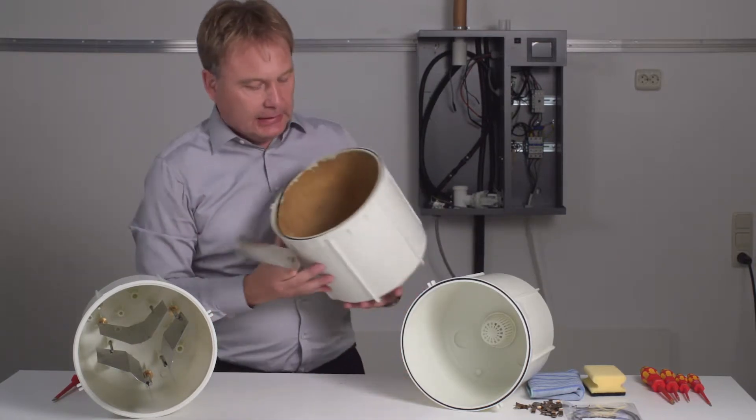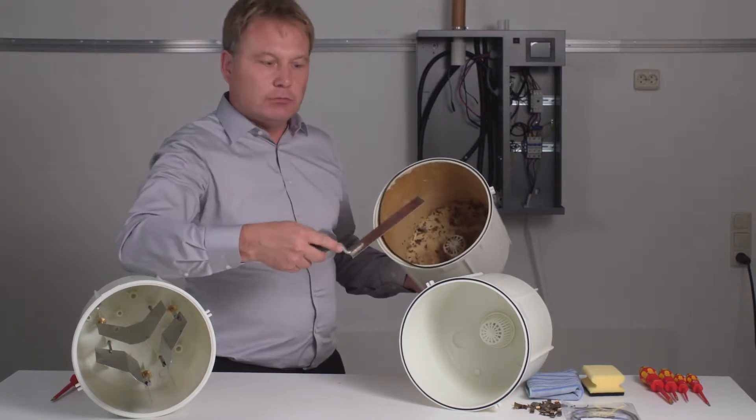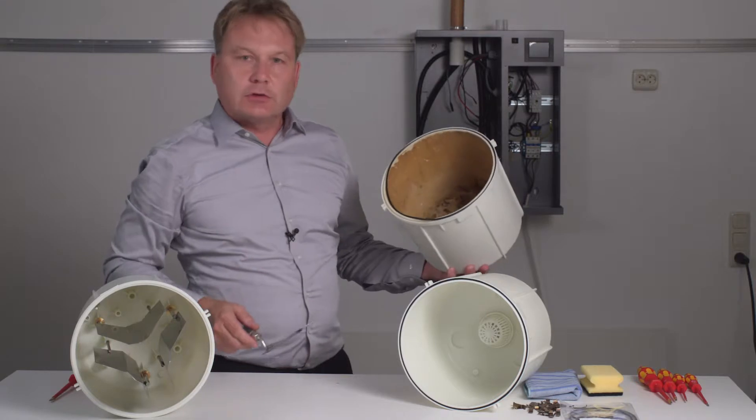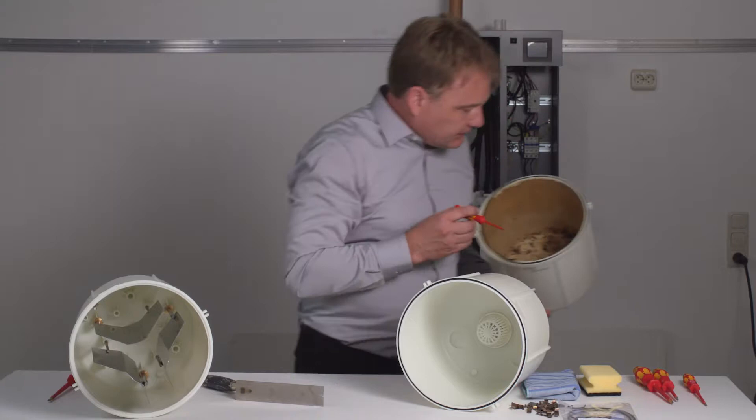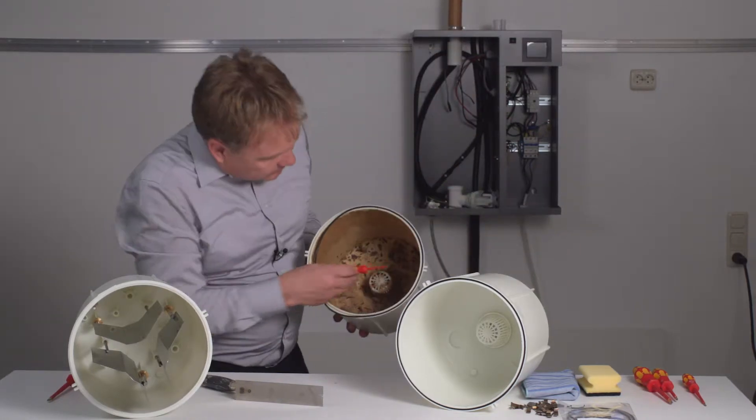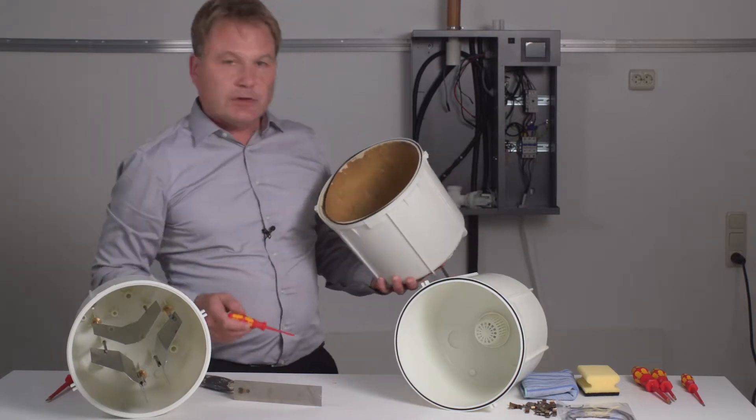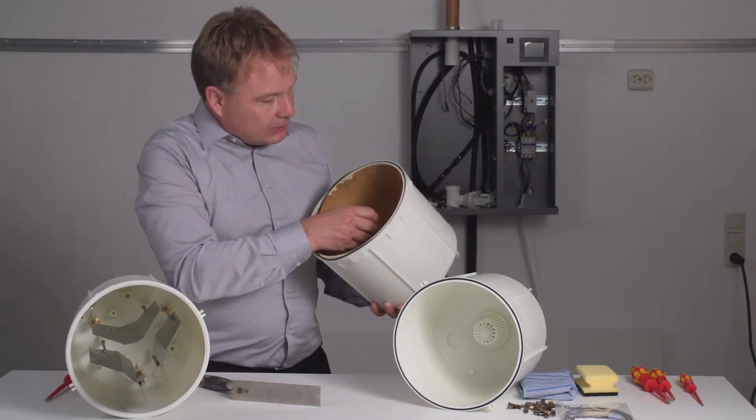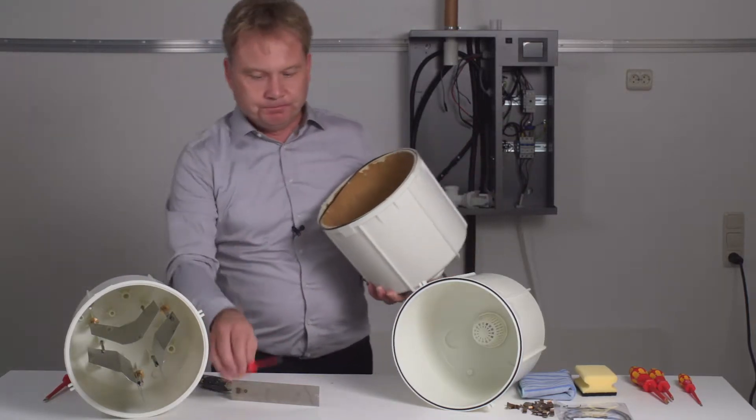The coarse particles of encrustation inside the steam cylinder can simply be scraped off using a spatula. Please also make sure that this strainer that stops the coarse particles is always clean. Take a small screwdriver and clear all the little holes so that the water can pass through again.